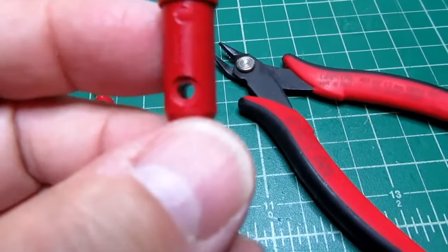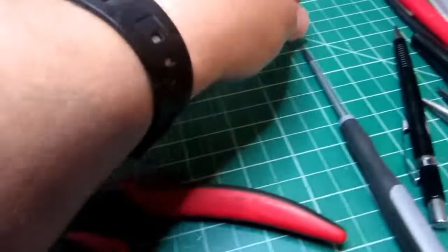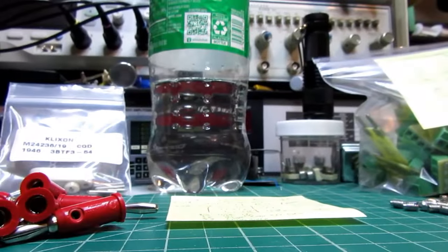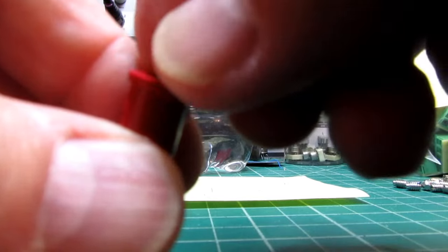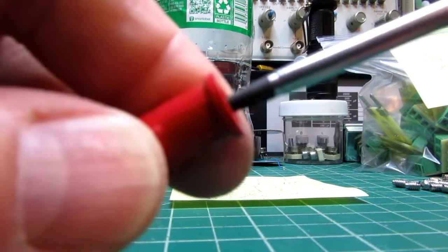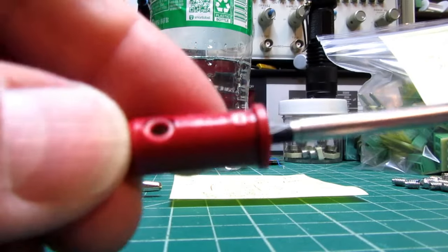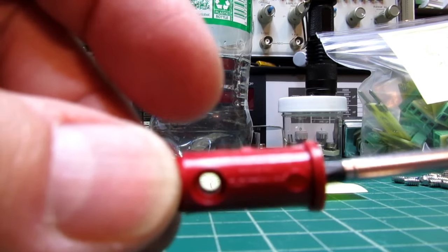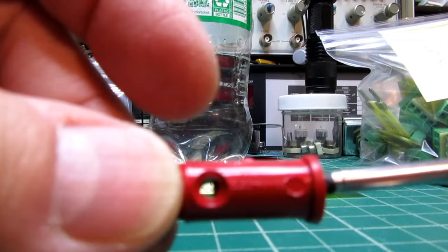These use side entry for the wire to allow stacking from the rear, and they come from Pomona with the set screw loose, and you basically just drop it in the back, stick a screwdriver in there, and turn it until I start seeing it enter the hole there.